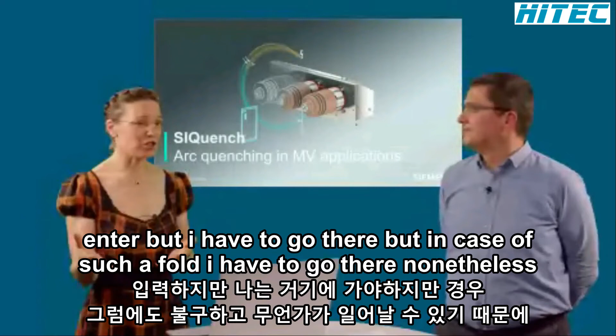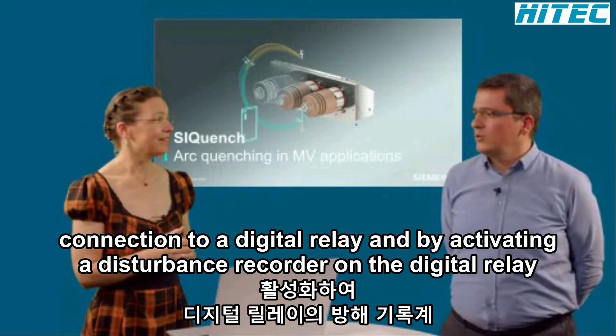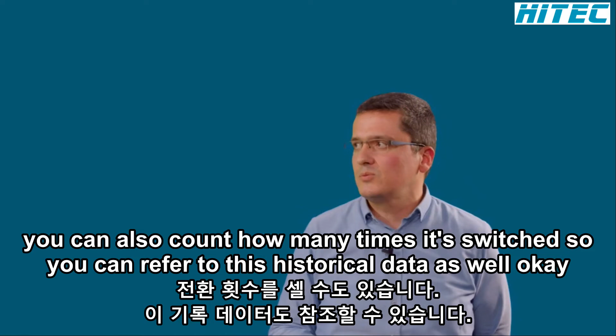Oh, okay, so no transfer to any kind of control center, I have to go there? Yes. But in case of such a fault, I have to go there nonetheless, because something might happen to the compartment, right? Actually, by having a hardwired connection to a digital relay and activating a disturbance recorder on the digital relay, you can also count how many times it switched. So you can refer to this historical data as well.